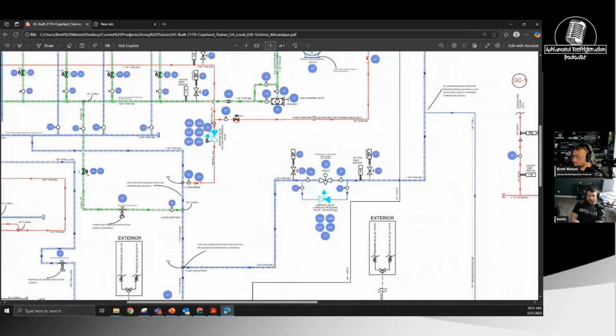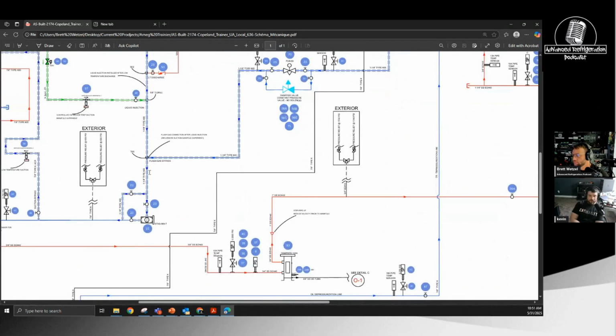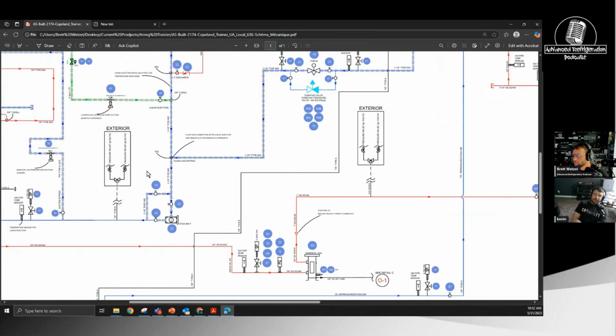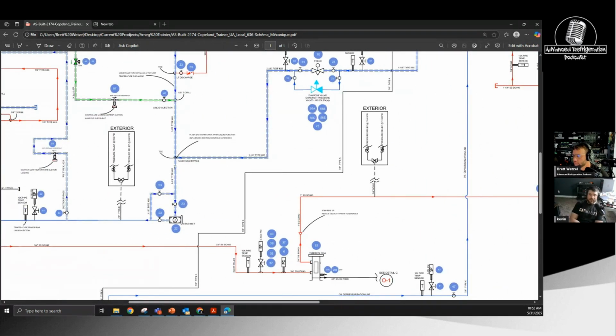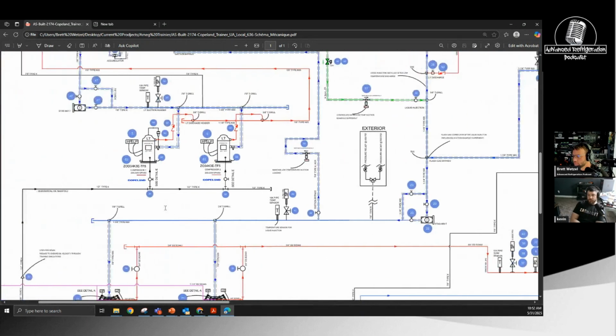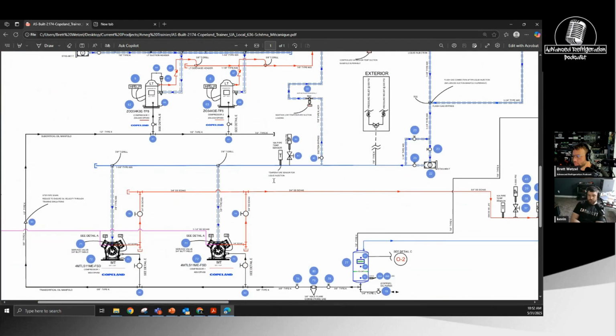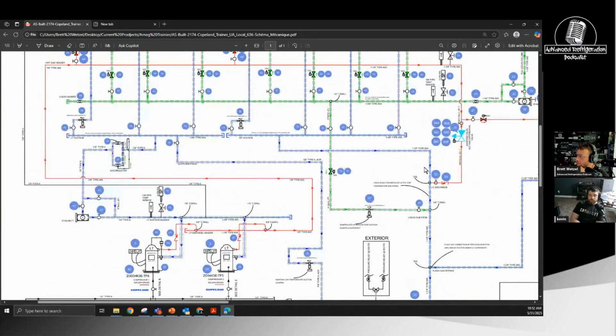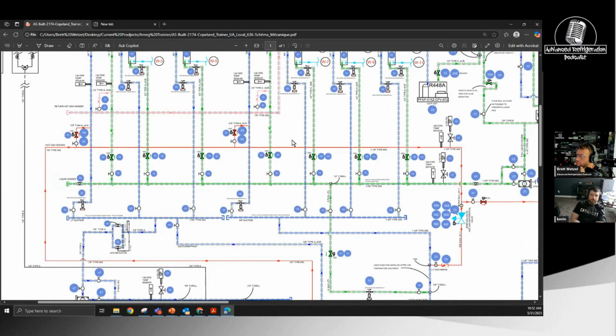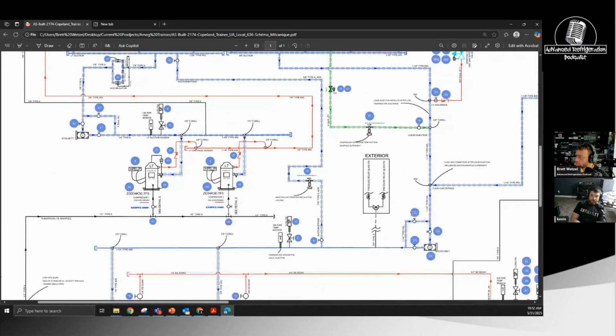So dumping out of here, we dump back into our main suction. Now, this rack had bypasses around every filter dryer and the oil separator. It doesn't show it on the oil separator, but they had one there too. Yeah, so right here, there's your filter dryer going down to your suction there. And then it looks like this is the part of the suction where you're getting all the returns for all your loads, whatever they might have been. Yes. Then we had, on both suctions, stepper valves for liquid injection.